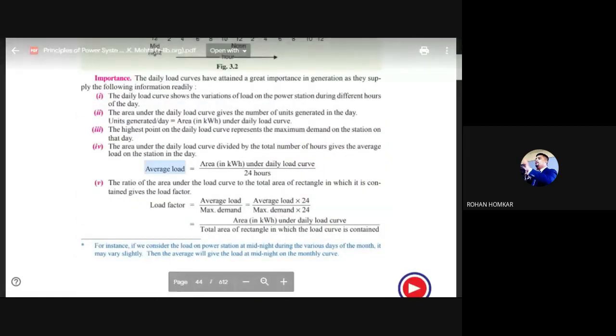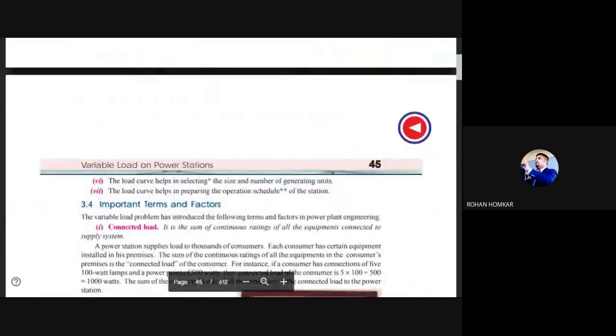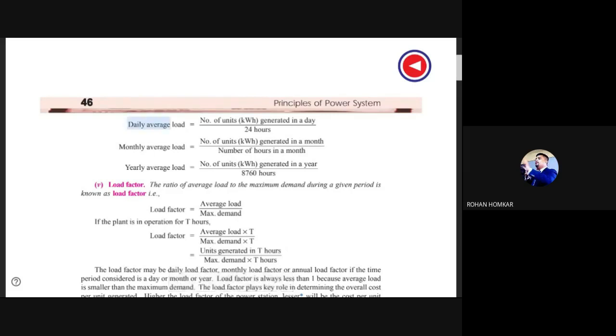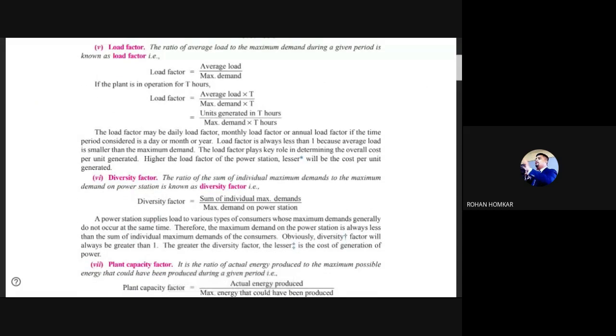Average load is the average of loads occurring on the power station in a given period of time. We have classifications: daily average load, monthly average load, and yearly average load. All these are calculated in kilowatt-hours per hour — how many kilowatt-hour units are generated and sold per hour. Load factor is again average load divided by maximum demand.